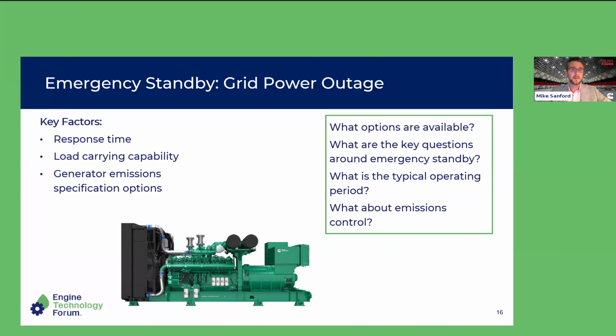That drives the requirements for what those on-site reciprocating engine generator sets may look like. It's typically critical that they have a relatively fast response time, able to start up and offer load or support to the loads on site as quickly as possible. In most cases, that's under 8 seconds or so from the time they're called to the time they're providing power and have brought that facility back online. Most data centers operate on an uninterruptible power supply, or UPS, for that short period so they don't suffer a true outage, but a longer duration outage could be carried by a generator set.